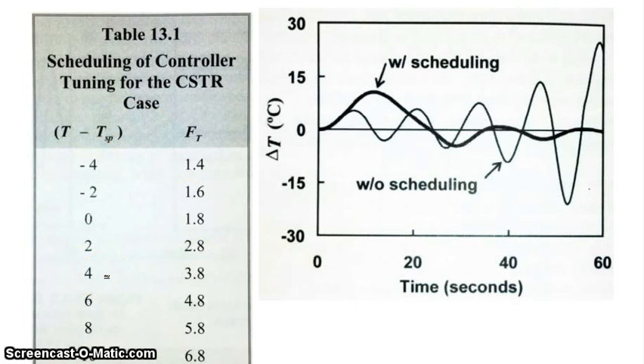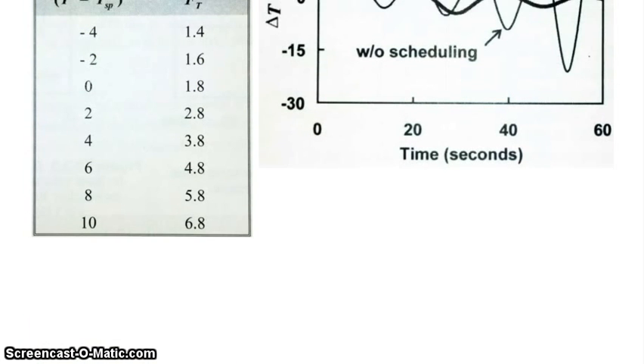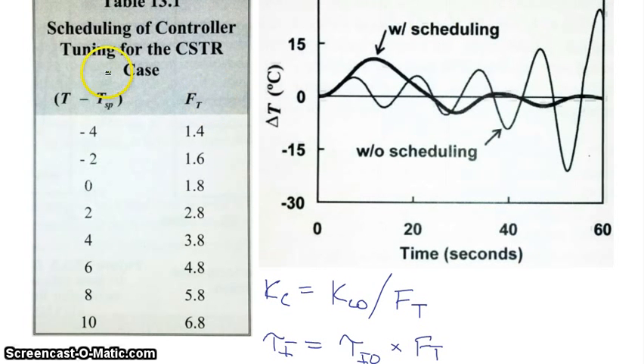And so your PID controller parameters will be functions of this particular process variable, this process variable measurement. So the way that works is that you would say, okay, I'm going to make my proportional constant Kc equal to some Kc0 divided by this tuning parameter FT. And so with this kind of scheduling, the PID control parameters change depending on the value of this process measurement according to this schedule or this table.